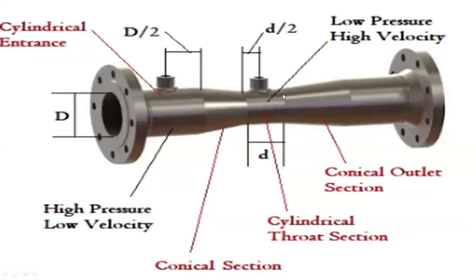There are two tappings on the venturimeter for pressure measurement. The upstream pressure tapping is located at a distance of one-half of the diameter upstream of the convergent entry, while the downstream pressure tapping is located in the throat, as we are seeing in this figure. The cylindrical entrance section for the venturimeter entrance is a straight cylindrical section with a length of five to eight times the pipe diameter.